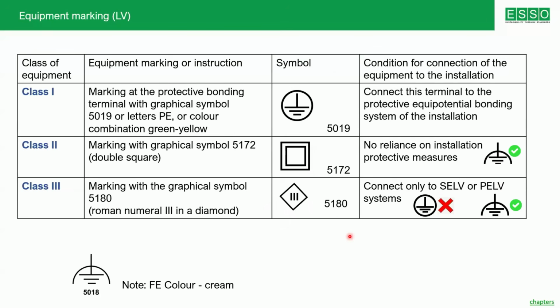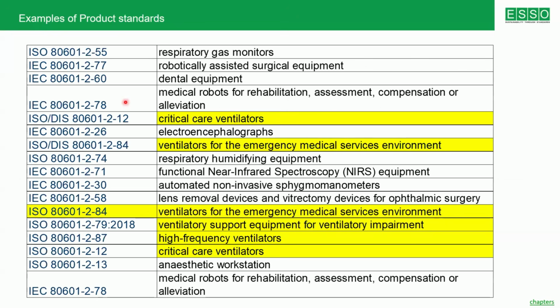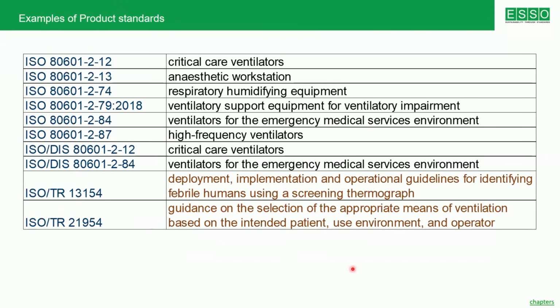The reference may be the neutral of the power supply, whereas for a class 3 equipment, the reference may be a functional earthing. It may not be the neutral of the system. So depending upon the type of equipment, the requirement varies, and these are very well explained in the respective product standard as well. The product standard, as you can see in the list, for example for ventilators, there are multiple types of ventilators, and each of these ventilators is made based on a typical standard. Either it's an ISO standard or an IEC standard, and the requirements are part of these particular standards. I'm just showing some examples.